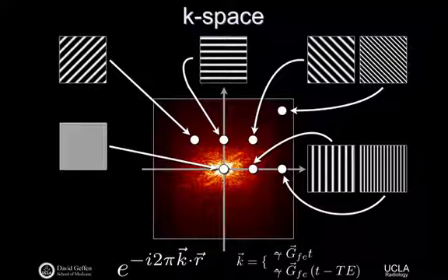So it's really helpful in MR if you have some understanding of what happens to my image if something happens in K-space. Because when you're sitting at the MR scanner, you're going to end up with an image that you don't like and have to think conceptually back to what possibly could have caused this. Now, the big challenge in a lot of MR is that lots of very different things can cause very similar artifacts. And so then you're left playing detective, trying to really figure it out.